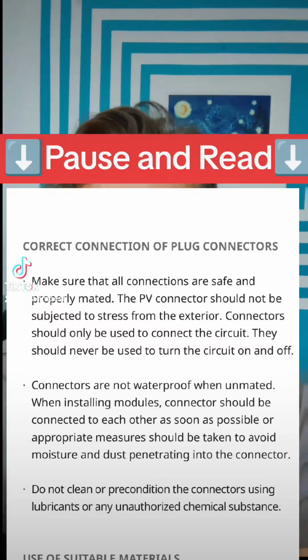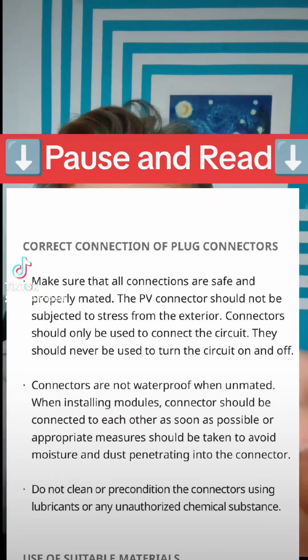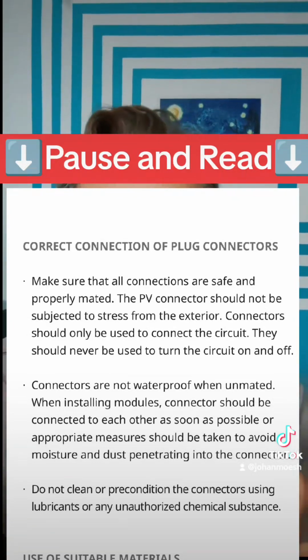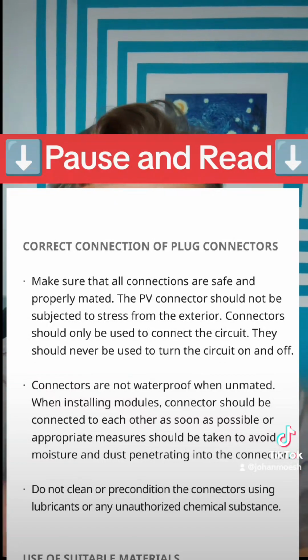And some of the inverters have exactly the same. You put your MC4 connections on. Let them, with every 4 panels, just give us a bucket of exactly the same MC4 connections. I did go through the warranties or the installation manual on the Longi panels, Canadian Solar, JA Solar and AE Solar. Nowhere does it say that if you disconnect, if you cut the wire, that it is void. Everyone says, look at the MC4. If they don't match, contact your supplier.